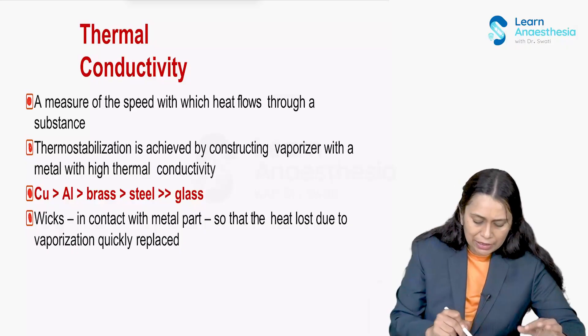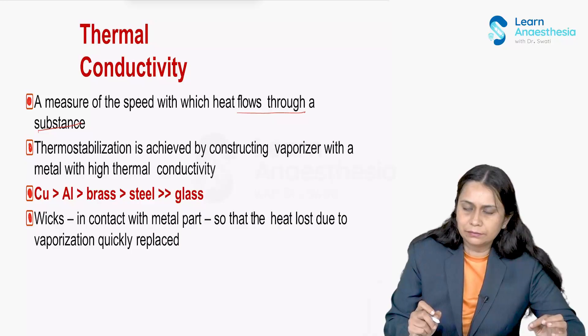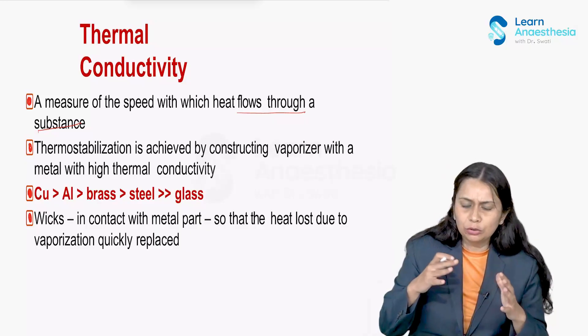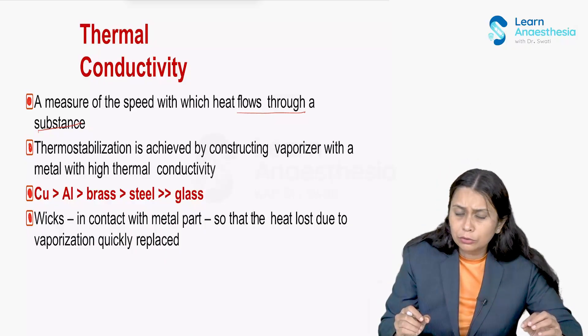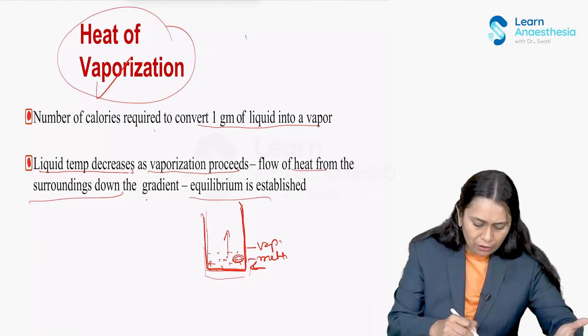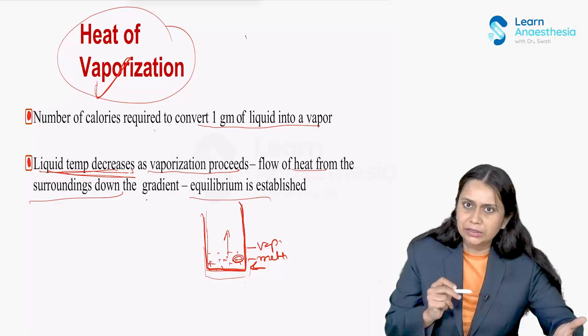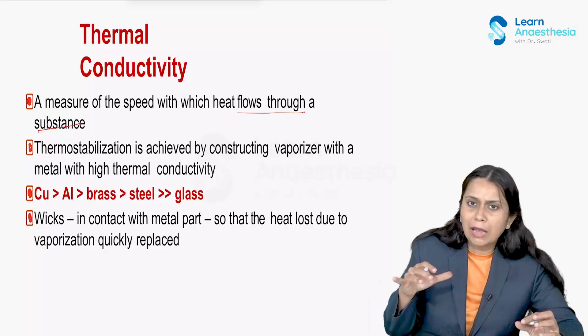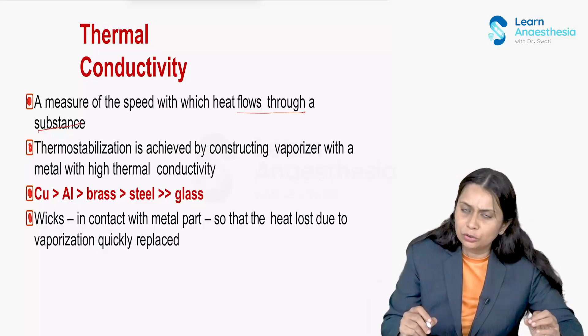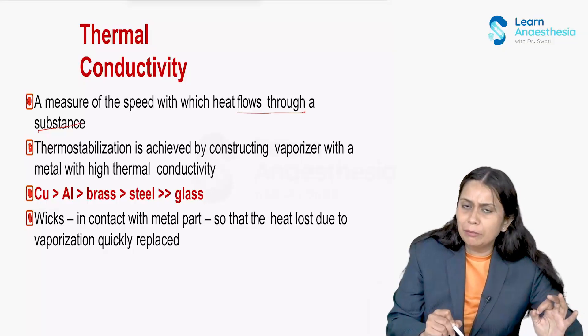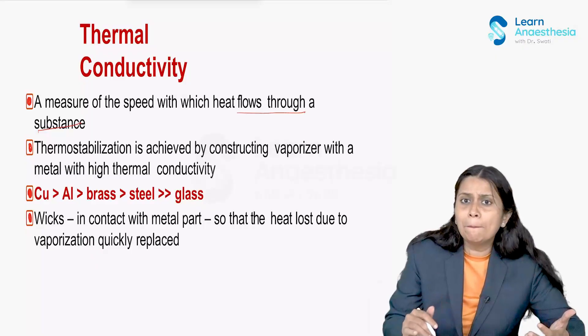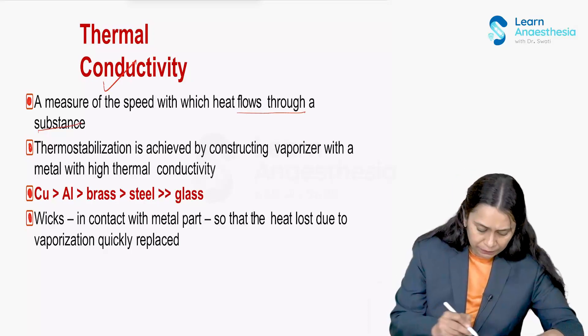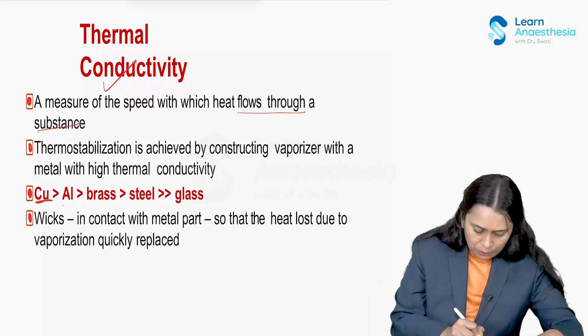Thermal conductivity is the measure of the speed with which heat flows through a substance. The metal with which the vaporizer is made should have high thermal conductivity to compensate for the temperature loss due to heat of vaporization. As the liquid cools, heat should flow from the metal to the liquid to compensate for this temperature loss. Metals with high thermal conductivity allow this compensation to happen faster. Copper has the highest thermal conductivity, followed by aluminium, brass, steel, and glass.